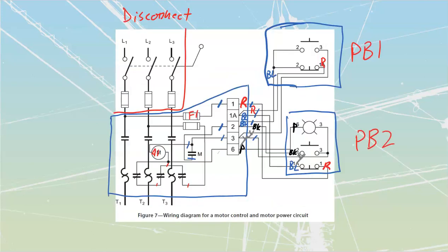Let's go back to this one over here, and I just want to do a quick little wire count with you to highlight what we have done. How many wires did we need to the small station? 3. Count that underneath the yellow highlighter over there. You see that there is a total of 3 wires that you needed to pull over to that station. Pull them now, identify them, you can sort them out later, if you were doing this as an install. Same with this one over here.